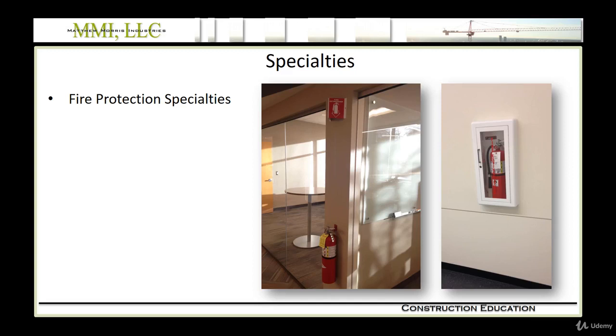The point is, depending on the fire hazard, the fire is extinguished in a different way, and the contents inside the extinguisher are either dry chemical, halon, water, foam, or carbon dioxide for different purposes. And the extinguisher needs to be labeled as such, describing the classification. And it also is labeled to show the capacity and the effective area that it can cover when it's used. Okay, to cap this off, often a fire extinguisher sign needs to be mounted above the fire extinguisher, and you can see that on the left.